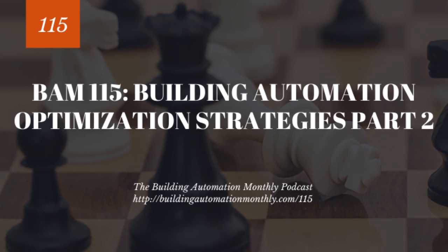Essentially, what you do is you've got a discharge air static pressure set point, and this is traditionally used with VAV systems. So you've got an air handler with a VFD on the supply fan, and you've got VAV systems downstream of the air handler, opening and closing their dampers. What happens is when the space temp gets above the space temp set point, at a certain point, a comparator will be triggered, and that's a programming logic block once again. A comparator is triggered, and that triggers a call for cooling.